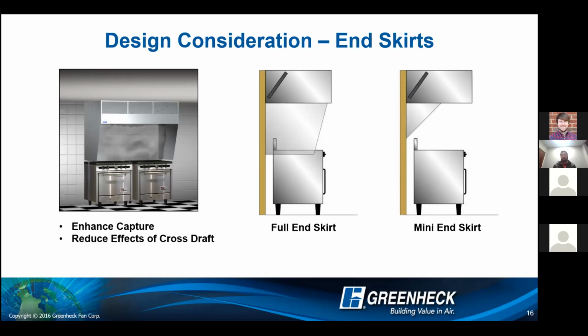Now, an important note with mini end skirts: that does not eliminate the overhang requirements. If you had full end skirts on the left and the right-hand side of this hood, that would be just like a wall, and you could have 0 inches of clearance from the appliances to the edge of the hood. With a mini end skirt, you would still need 6 inches from the edge of the appliance on that side.